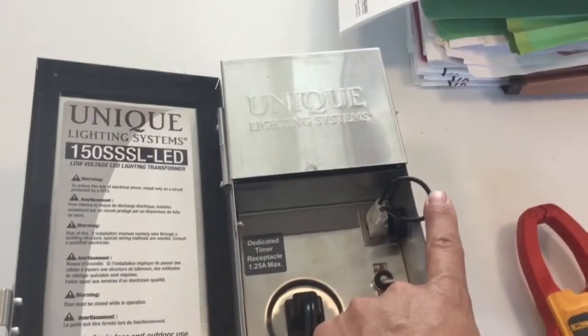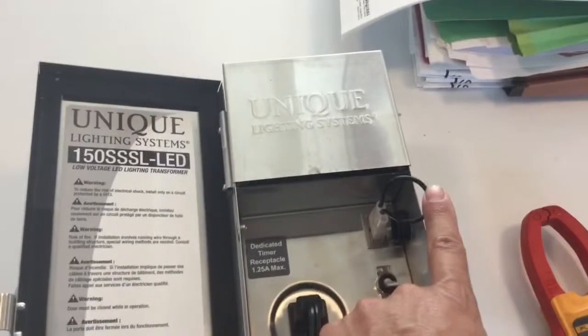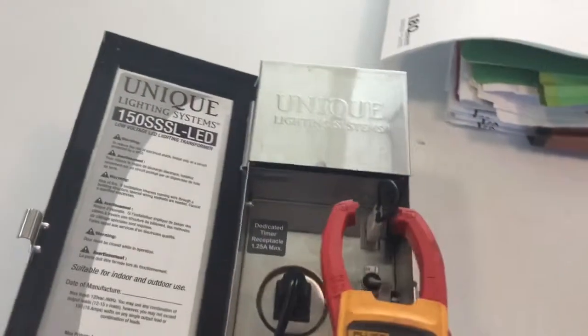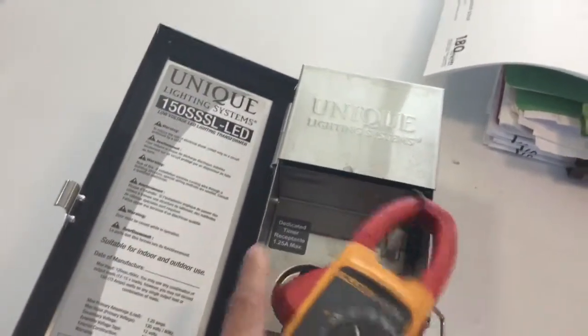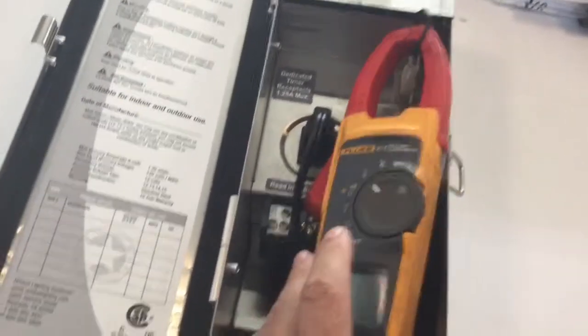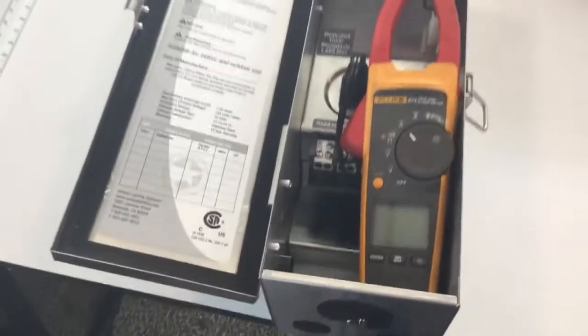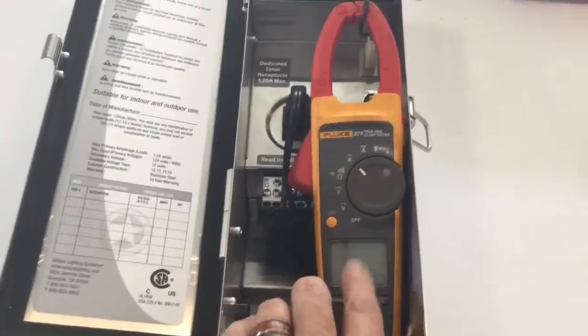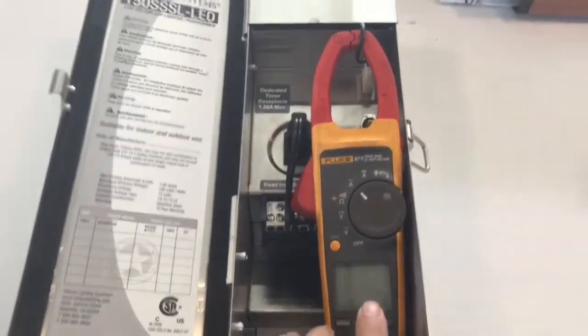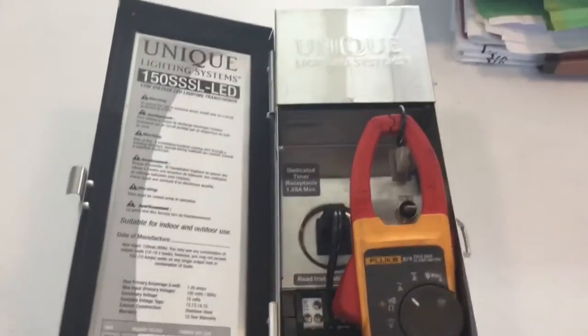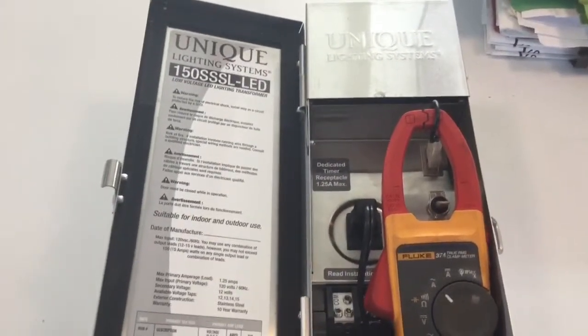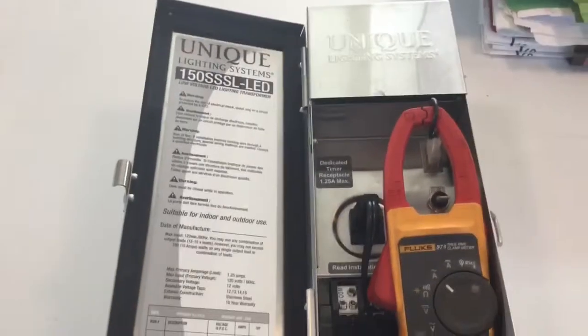And as you can see, as I'm playing with it, it's got an oversized loop on it. And we oversized that for a reason, because what you're going to do is take your amp probe and actually put it right through the loop and close it down. Once you do that and you've got everything dialed where it needs to be, you're going to get a readout on that screen. Now again, I've got nothing plugged in here, so I'm not getting a readout, but you'll get a readout. And if you get a readout that says 0.5 or 0.7 amps, you're well under the 1.25 rating that's on this transformer. So there's plenty of room to add to it.